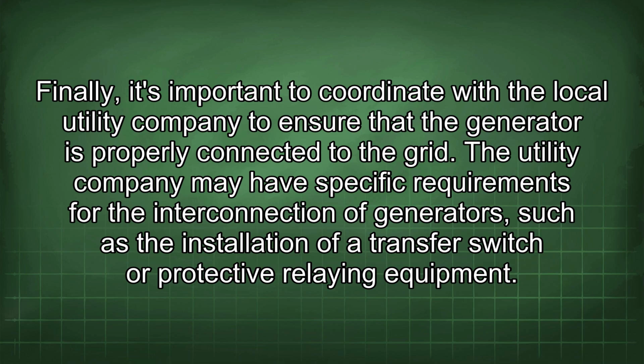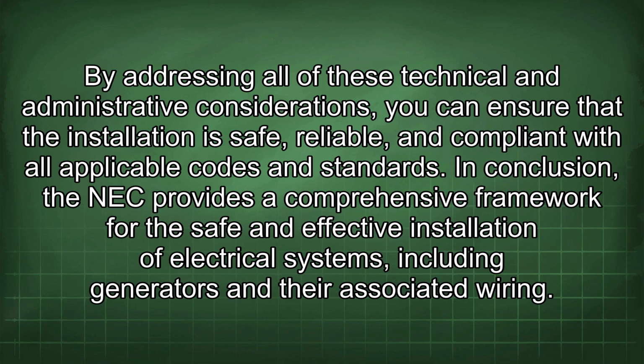Finally, it's important to coordinate with the local utility company to ensure that the generator is properly connected to the grid. The utility company may have specific requirements for the interconnection of generators, such as the installation of a transfer switch or protective relaying equipment. By addressing all of these technical and administrative considerations, you can ensure that the installation is safe, reliable, and compliant with all applicable codes and standards.